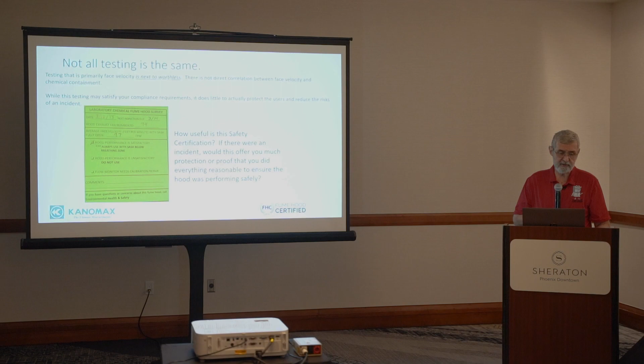How many of you have seen a label like this? These are pretty much worthless, yet we'll see them on hoods all the time. What did they do? Look at the date—they did the test back in '13, and it says this hood has 97 feet per minute, so it's safe. Not. Our more elite testers refer to the testers who do this kind of testing as 'lick'em stick'ems'—they basically take a velocity reading, stick the label on the hood, and they're done. A lot of owners accept that as acceptable, thinking 'I had my hood tested, so I'm fine.' But if you ever have an incident that goes to court and this is all you've had done, you're going to have problems.